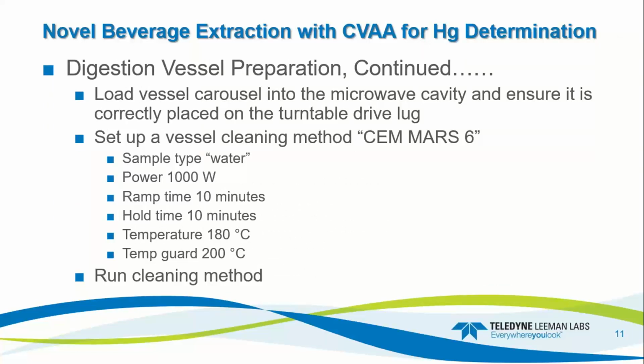Load that carousel onto the microwave, put it in the cavity, ensure that it's correctly placed on the turntable drive lug, and then you want to set up a vessel cleaning method. For the CEM Mars 6, I chose sample type water, power 1000 watts, ramp time of 10 minutes, hold time of 10 minutes. My temperature, I ran it up to 180 degrees C, and I used a temp guard at 200 C. So if it goes above that 200 for any one of the vessels, it will shut down the program. And then you go ahead and run that cleaning method.